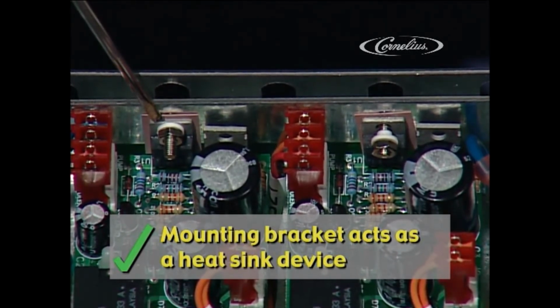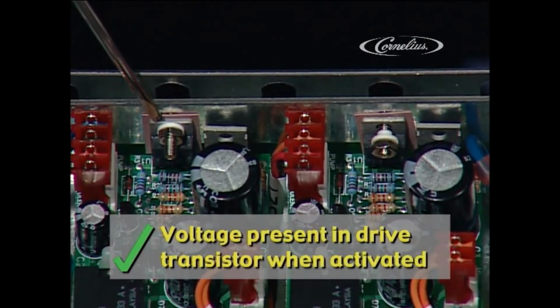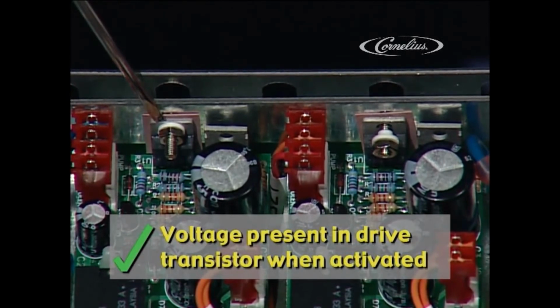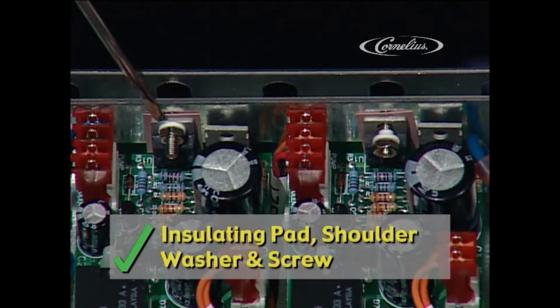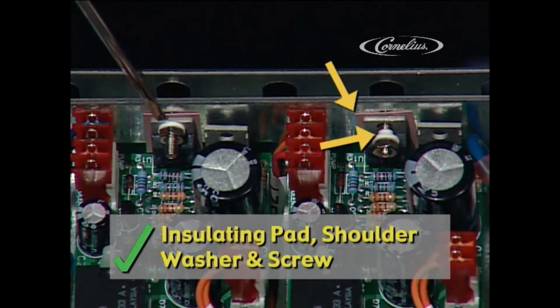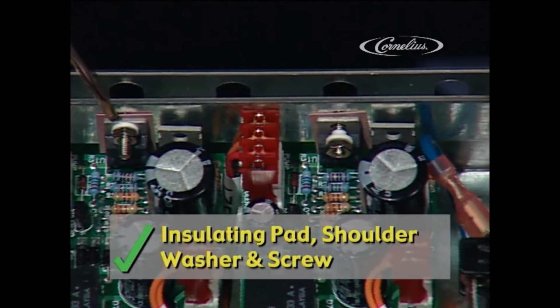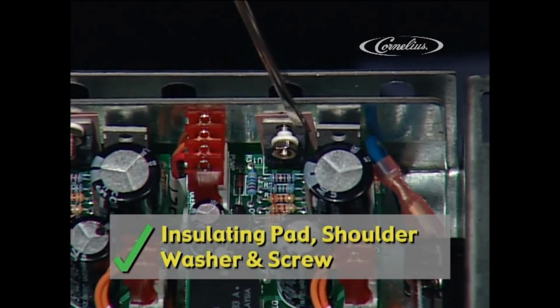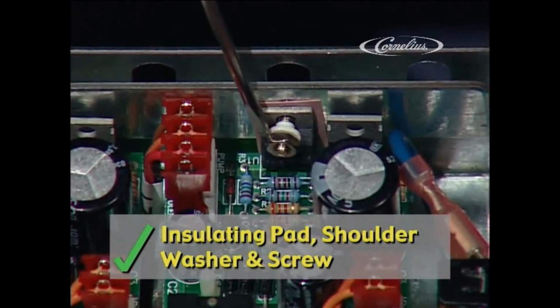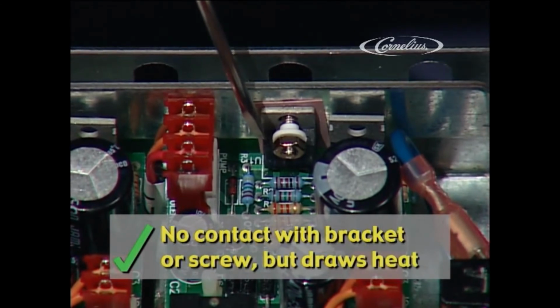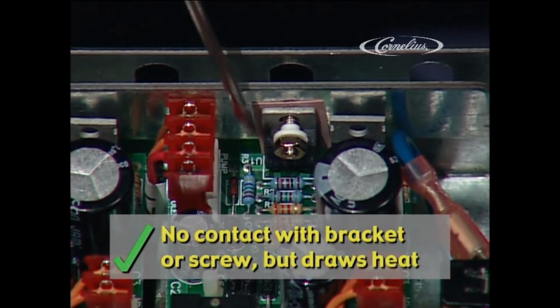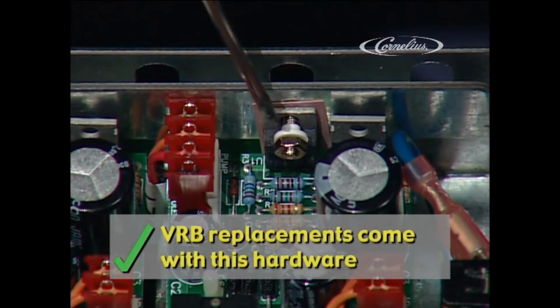However, there is another, more important reason for this hardware. Because voltage is present in the drive transistor when it's active, we must ensure that we are not grounding it through the chassis, as this will cause a short circuit and damage the VRB. We do this by means of this insulating pad and shoulder washer and screw. These parts must be present and in the correct order. The shoulder of the washer goes up inside the hole in the drive transistor and the pad in place between the bracket and the chip itself. This will ensure no contact with the bracket or the screw, but still be able to draw the heat. Every VRB replacement board comes with this hardware.